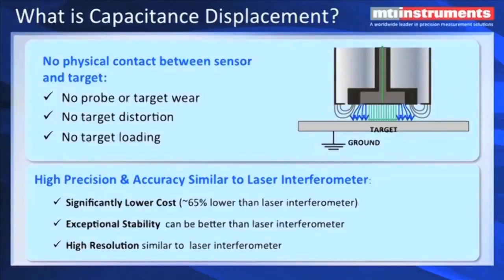If we look at the electric field lines there, we can see that the center lines are very straight, going perpendicular into the target. And then we also see fringing fields that are off to the sides, and also one generated by the guard, which we'll talk about in a little bit. What's important about non-contact capacitive displacement measurements is that there's no physical contact between the sensor and the target. So there's no wear, there's no loading, and you also don't have any distortion of the target. Whereas contact probes would push on a target and could actually bend it a little bit.